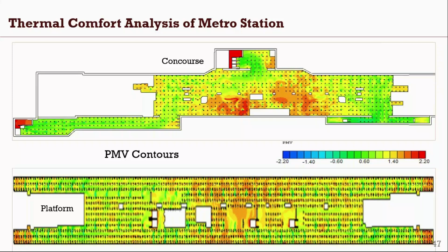Last one, mean age of the air, which can be found from CFD. Mean age is a significant indicator of the freshness of air in a room - how the air coming from outside is changing. That's the time called mean age of the air. It is very much required in hospitals and ICU facilities so that fresh air can circulate as quickly as possible. It is also required in natural ventilation studies - you can find if it's forced ventilation, and also find the air change per hour, and accordingly select your options.